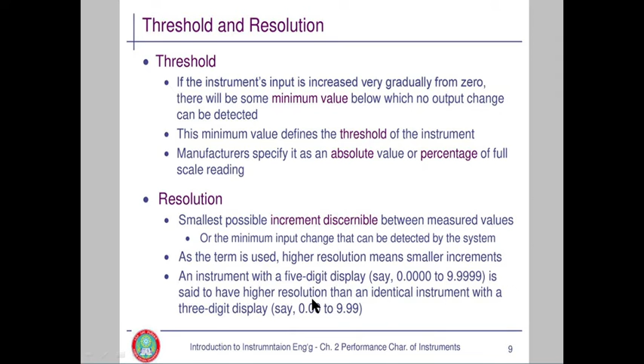An instrument with a 5-digit display, say 0.0000 to 9.9999, is said to have a higher resolution than an identical instrument with a 3-digit display, say 0.00 to 9.99. So here it is divided into 5, there it is divided into 3. With a 5-digit display, a smaller increment can be recorded, so it has a higher resolution compared to the 3-digit display. Okay.